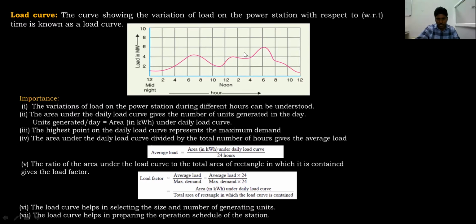Maximum demand on power station is, you can see here, the total peak: 6 megawatts is the maximum demand of the power station. So directly by seeing the load curve itself, we can say the maximum demand on the power station. And then the area under the load curve. Area means you see this x-axis, y-axis: megawatts into hours. So area under the curve units are megawatt hours or kilowatt hours. You can express in anything, kilowatt hours or megawatt hours, which gives you units generated in a day, total 24 hours.